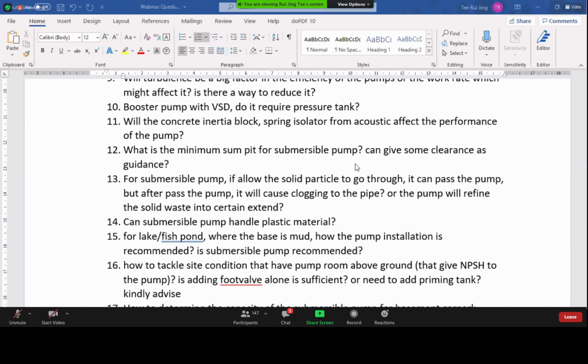So in correlation to that, your pit sizing has to take into account the depth of the pump as well as the volume that is needed to pump out. Yeah, there's a formula for sizing this type of pit against the flow rate of the pump. So if you need that, then we can send it to you. I hope that gives at least some basic information on this method.